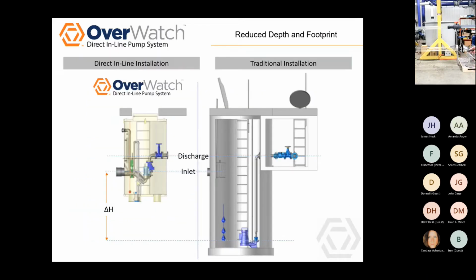Talking about the installation advantages, because we lift fluid directly from the invert, you can save excavation depth in new installations with this system. You don't have to dig as deep. If you're worried about groundwater or bedrock, this is a way to reduce those issues. You see the OverWatch system on the left versus the traditional submersible system on the right. We're typically saving at minimum 6 to 8 feet of excavation depth because we don't have that retention storage needed to keep the pumps cool.